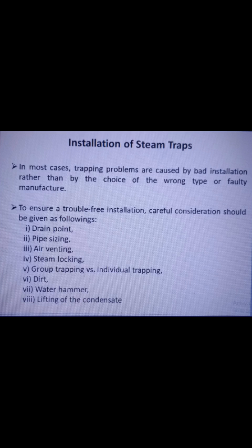Second one is pipe sizing. The pipes leading to and from steam traps should be of adequate size. This is particularly important in the case of thermodynamic traps, as I have already discussed in my previous lectures. This is because their correct operation can be disturbed by excessive resistance to flow in the condensate pipework. Pipe fittings such as valves, bends and tees close to the trap will also set up excessive back pressure in certain circumstances.